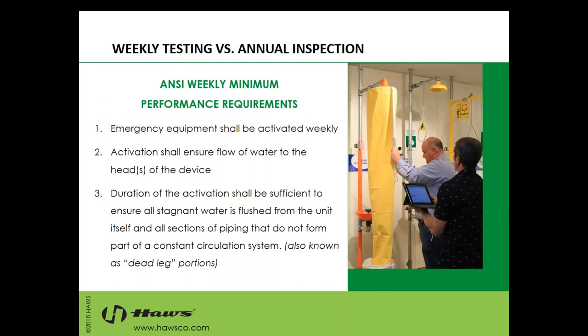Now, weekly testing is another important change, and it is so simple. On the right, you can see our 9011 test kit that they're using, and the following steps are very simple. First, the emergency equipment needs to be activated on a weekly basis. The activation needs to ensure flow to the heads of the device. That's it. Water needs to be coming out of the shower. Water needs to be coming out of the eye face wash, and the duration of that activation needs to be long enough to clear the dead leg.